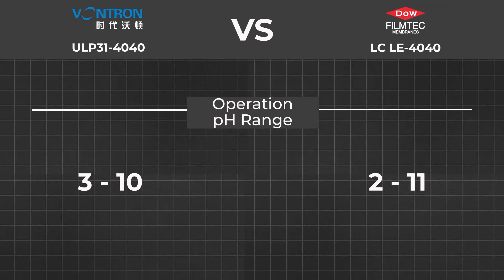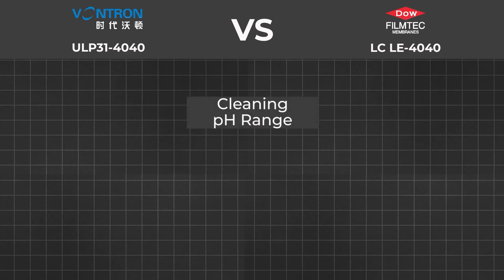Operation pH range: Vontron ULP31 working pH range is 3 to 10; Filmtec LCLE4040 working pH range is 2 to 11. Normally tap water pH is in the 6 to 7.5 range — the wider range is useful for membrane cleaning with acidic or alkaline chemicals. Cleaning pH range: if you want to use your membrane longer, it is better to add a CIP (Clean In Place) system, which automatically washes the membrane inside the housing. Vontron cleaning pH range is 2 to 12; Filmtec is 1 to 13.